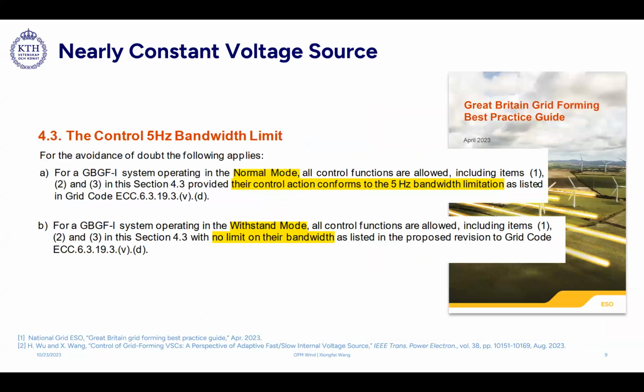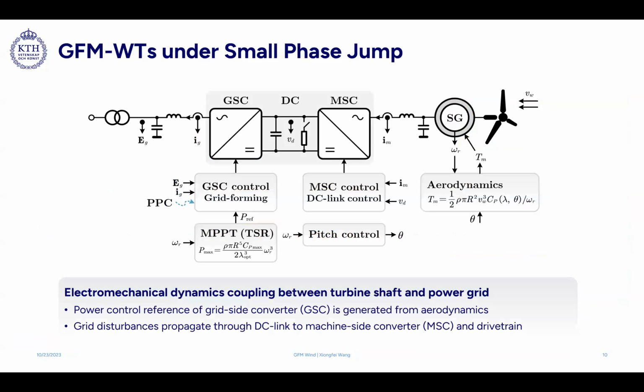And if we look at the latest best practice guide released by National Grid, here we are basically aligned with each other. For normal operation mode, we can maintain a nearly constant voltage source. So that's why in this best practice, and also the grid code, they mention the control action should be within the 5 Hertz control bandwidth for the outer loop. In this way, we can make the source as slow as possible, so we can keep the voltage phasor nearly constant. However, if we operate in the withstand mode under large disturbances, we should have no limit on the control bandwidth. This is also aligned with the large phase angle jump dynamics.